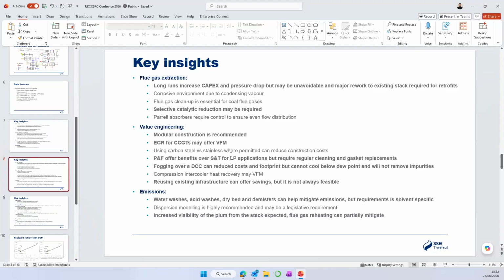Plate and frame heat exchangers offer space, cost and pinch temperature benefits over shell and tubes, but require shockingly regular cleaning and gasket replacements. That has a massive maintenance burden and exposure risks to your operators, so that needs to be considered. Fogging over DCC can reduce cost and footprint, but you're limited by how much you can cool your flue gas. Basically, it won't go below the dew point and doesn't remove any impurities.